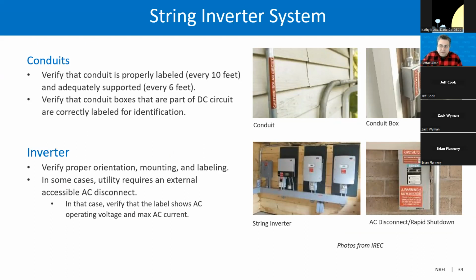The second thing is the conduits. As we discussed, the conduits carry DC, and the conduits must be properly labeled every 10 feet and adequately supported at 6 foot intervals. This is different from the AC conduits. They need labeling. So the conduit boxes that are part of the DC circuit must be correctly labeled for identification, and inverters must be installed with proper orientation, mounting, and labeling.